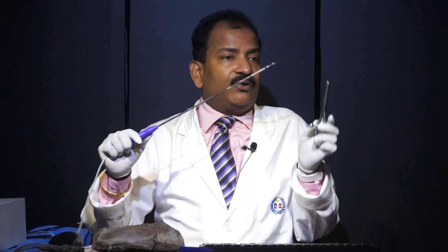First you go and hook and then you press, because if you already give a good contact, current will not jump from insulation. Just like you have a drain pipe in your house which is taking the rain water from the floor to the bottom, and if it is broken at one or two places, a small break, but if the free flow of water is there, it will not leak. But if you stop it from the bottom, then it will start spraying out under pressure. So, never activate your paddle in open circuit.